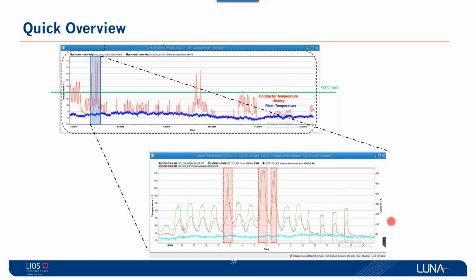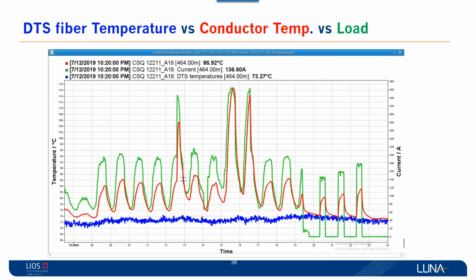So from a resiliency point of view, the client should be able to know that they cannot keep operating it, even though the duct bank temperature seems fine. Without fiber, they would never have known that they're actually operating at a much higher load than the cable was rated for. A quick zoom in to look at this data.